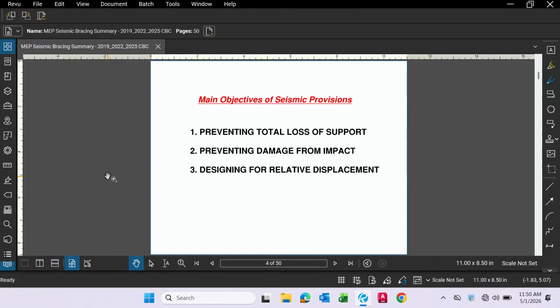One is to prevent total loss of support. Second is preventing damage from impact, components hitting each other in a seismic event. And three, which is a little bit harder to control, but we'll go over the details in a minute, is the design for relative displacement. What it means is, during a seismic event, things can move differently due to different natural frequencies. They can go in different directions, and we have to account for that relative displacement. We have to make sure that nothing gets pulled apart.